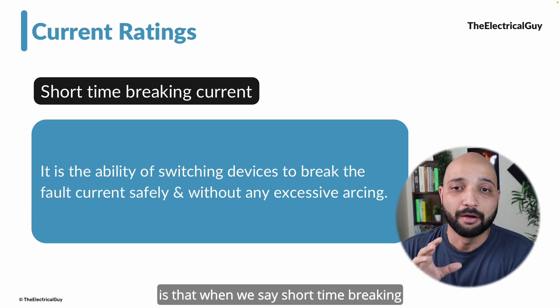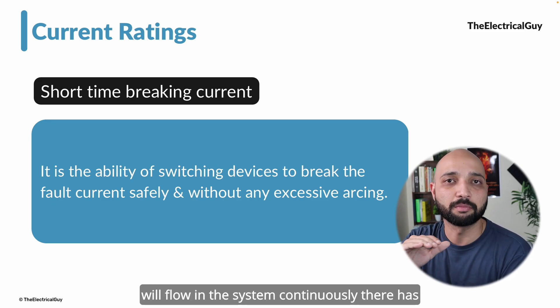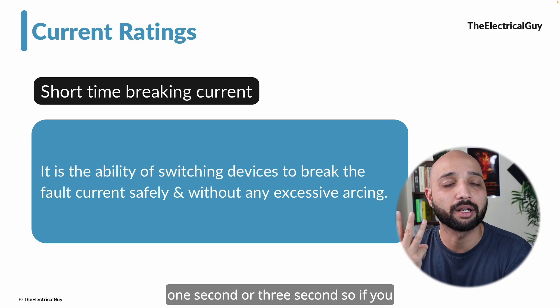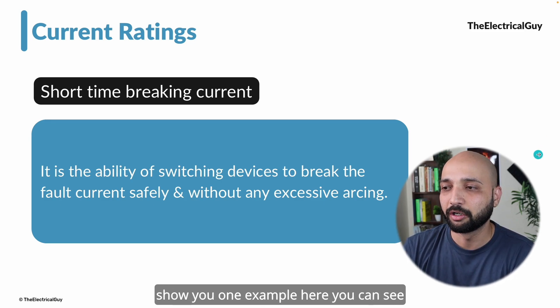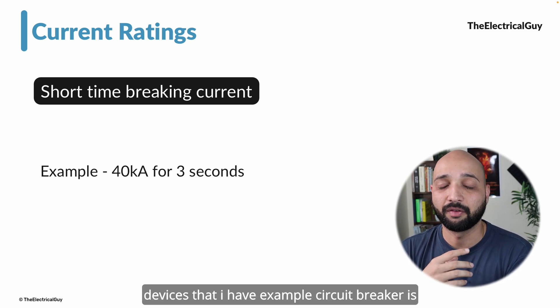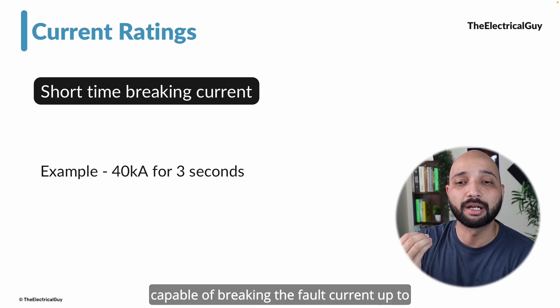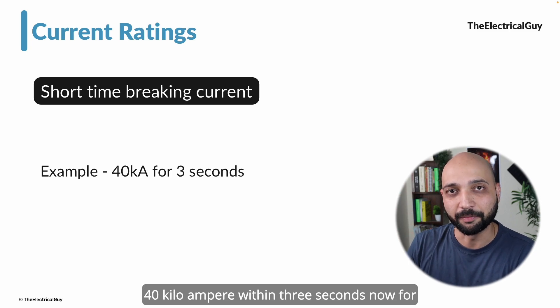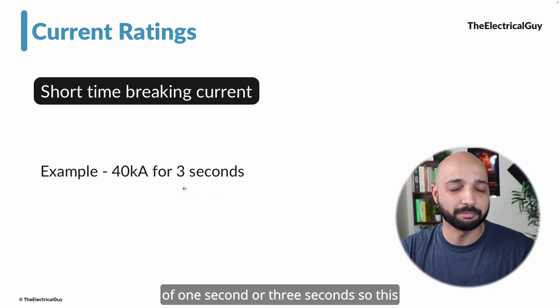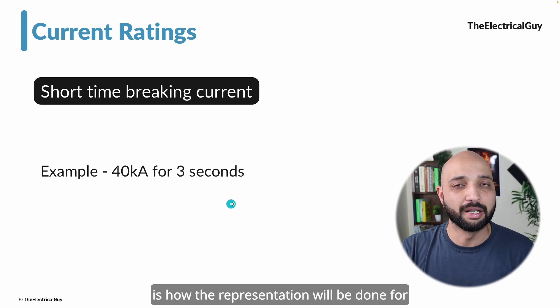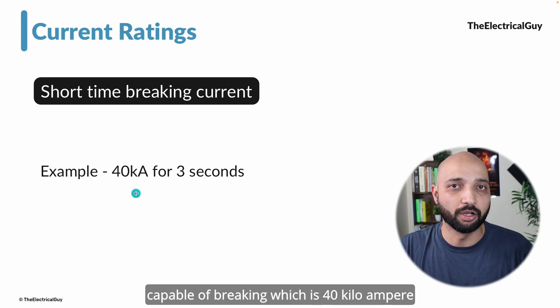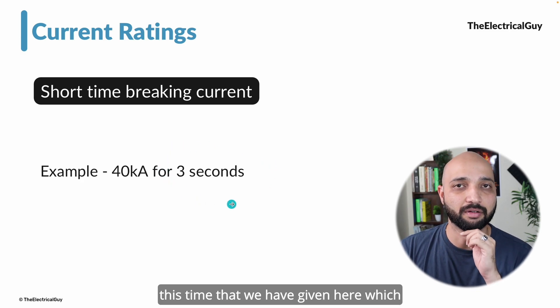One important thing to remember: when we say short time breaking current, we do not mean the current that flows continuously. There has to be a time limitation, and generally that time limitation is one second or three seconds. For example, a rating of 40 kilo ampere for three seconds means the switching device — for example, a circuit breaker — is capable of breaking the fault current up to 40 kilo ampere within three seconds. The circuit breaker will break the current very quickly in a few milliseconds, but to be on the safe side we assign a rating of one or three seconds.